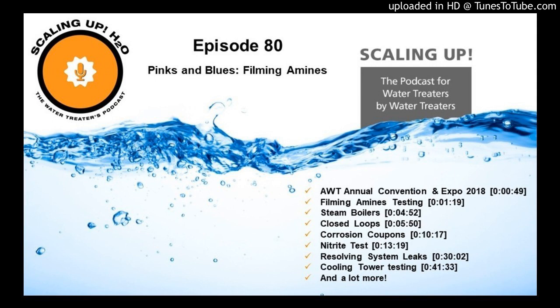So what we learned is that those two do not play well together, and since the AWT convention, I've been in my lab, and I can tell you that PTSA and Filming Amine are not linear. So I can't say add this much and you'll get this result, because it is all over the place. If there is an equation to figure that out, I have not figured that out yet.